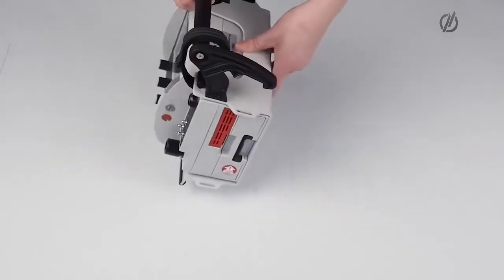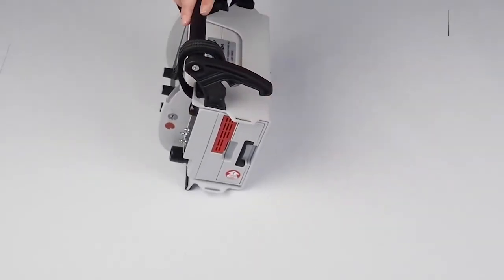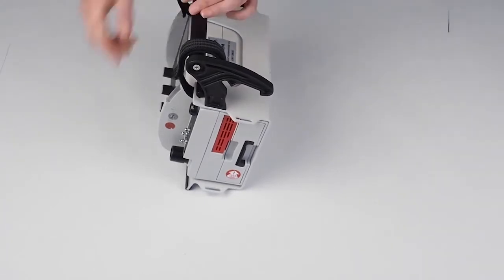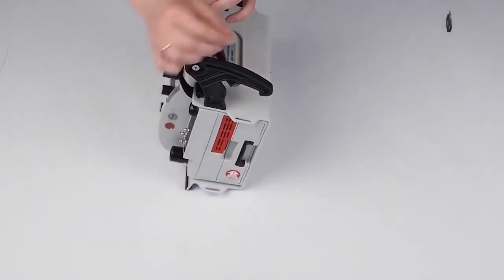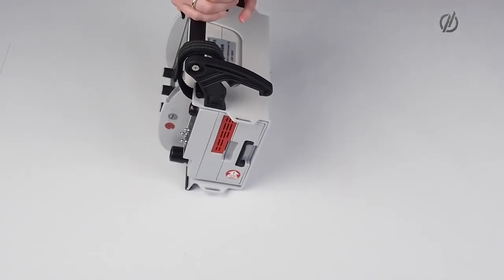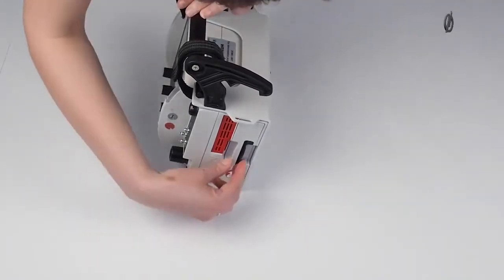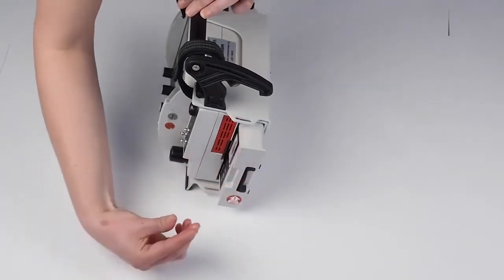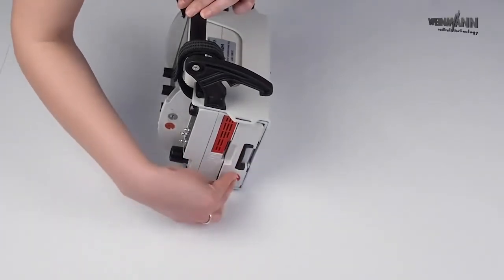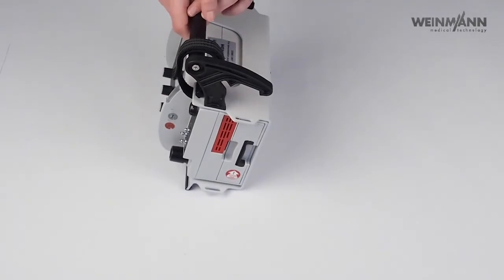And on the left-hand side of the device, we have our air intake via this hygienic filter that filters air coming into the device from virus and bacteria. And we have our internal battery, which lasts about 9 hours under standard ventilation and can be easily exchanged by just clicking like this. And when you plug in the battery, make sure that you always hear a click to ensure that the battery is safely inside.